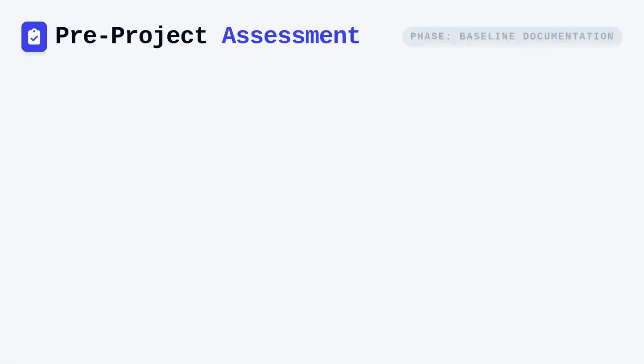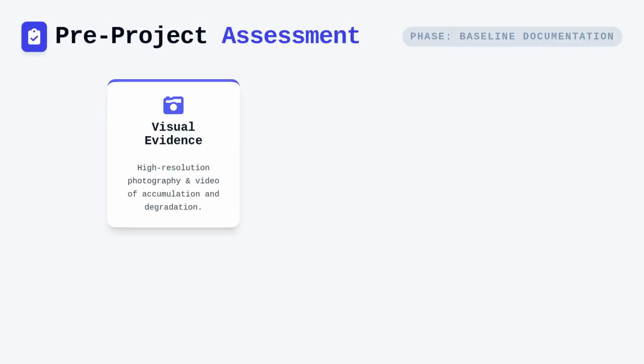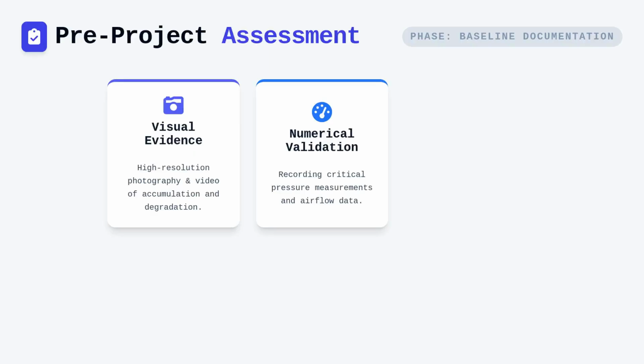The pre-project assessment serves as your baseline and must be exhaustive in its detail. You are essentially creating a snapshot of the system's condition prior to intervention to distinguish between pre-existing damage and any future issues. This documentation must include visual evidence, typically captured through high-resolution photography or video, focusing on areas of significant accumulation or degradation.